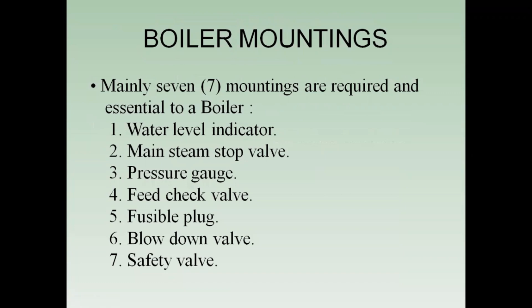Boiler mountings are the main parts of boilers which are mounted on the shell. There are mainly seven boiler mountings. Firstly, the water level indicator — it indicates the level of water in the boiler. Then comes the main steam stop valve, which controls the flow of steam from the boiler to the steam pipe. Then comes the pressure gauge, which is used to measure the boiler pressure. Then comes the feed valve, which regulates the feed water supply to the boiler. Then comes the fusible plug — it works as a fire extinguisher and prevents explosion due to overheating of the furnace plate.